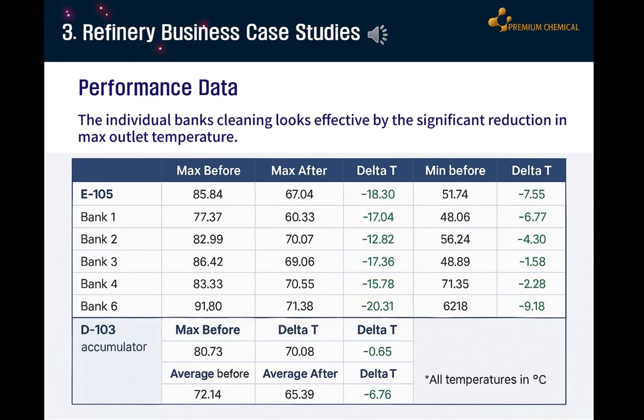After cleaning, the maximum temperature decreased by an average of approximately 14.84 degrees Celsius, indicating a significant improvement in heat transfer performance. Bank 6 had the largest delta T of -20.31 degrees Celsius, indicating that this bank had the highest contamination level. Conversely, Bank 2 showed relatively little improvement, suggesting less contamination or a limited cleaning effect.